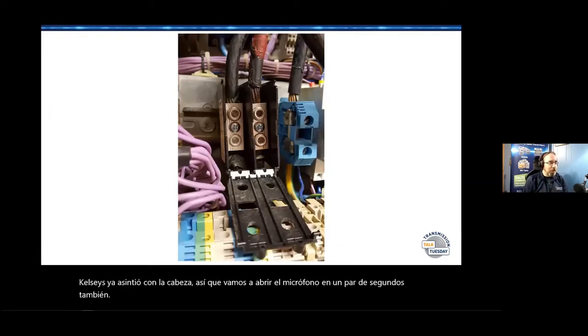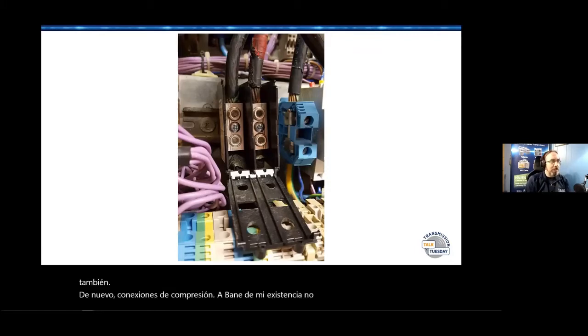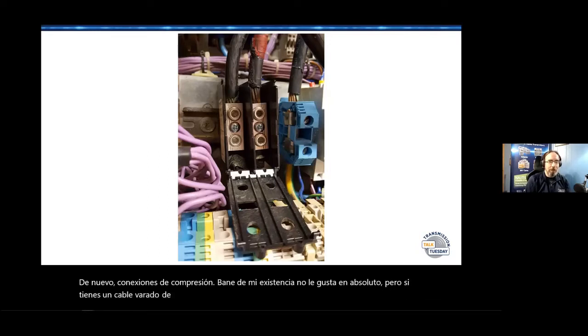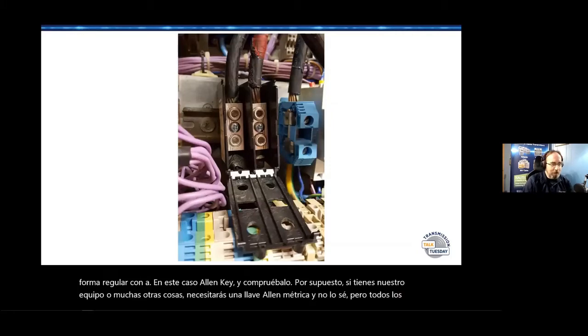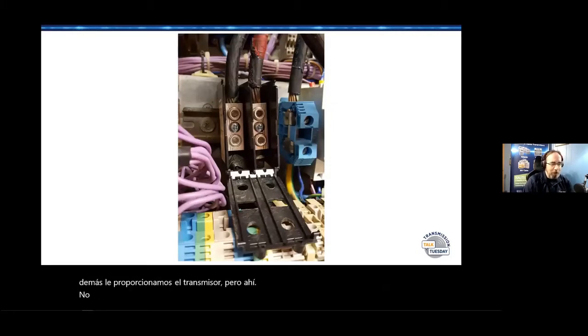Compression connections are the bane of my existence, I don't like them at all. But if you've got a stranded wire coming into a terminal block, that's how it's going to be tied down almost always. So you need to allow time to go in regularly with, in this case, an Allen key, and check it out. If you've got a certain brand of gear, you'll need a metric Allen key. We provide it with the transmitter, but they're not hard to get. Home Depot carries metric stuff too.